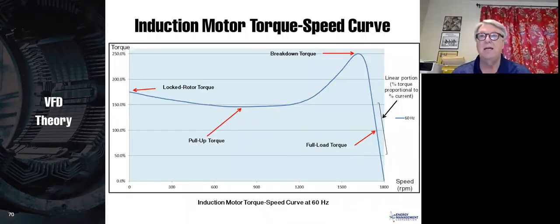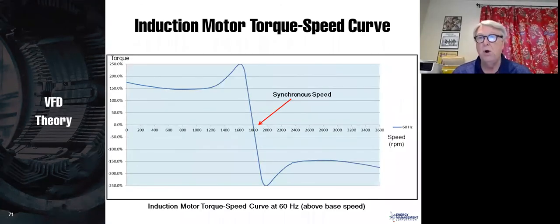This is an induction motor torque speed curve. I like to say that on a drive, motors never start, they only run. So this is the starting portion of the curve, up to generally we say about 150% torque here. And your motor will never see that when running on a variable frequency drive. I'll show you that in a moment.